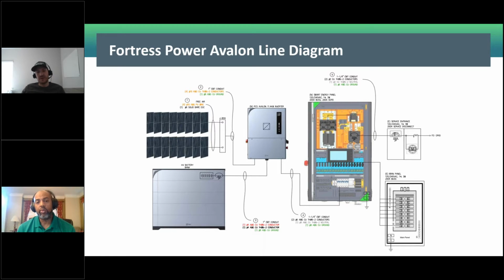That doesn't include relays and smart circuits for your EV charger and generator integration. This smart energy panel eliminates the need to rewire your service rated load center, because you have a 200 amp breaker you can add to the panel. If your load center has smaller amperage, like 150 amps, you can put a 150 amp breaker inside the panel instead.